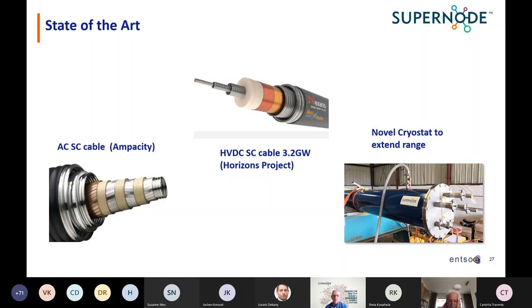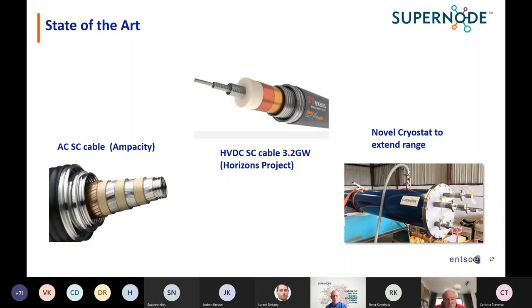On the right you'll see some of the work SuperNode are doing. The tape technology is where it needs to be technically, but the cryogenic cooling systems need to be further optimized, with their range and application extended — particularly in Europe where much of our power will come from the offshore arena. At SuperNode, over the last two years we've developed a system that has received a statement of feasibility from DNVGL. It uses a special type of metal cryostat with a very low coefficient of thermal expansion, critical because cooling to minus 200 degrees Celsius means contraction and expansion during cycling must be avoided.